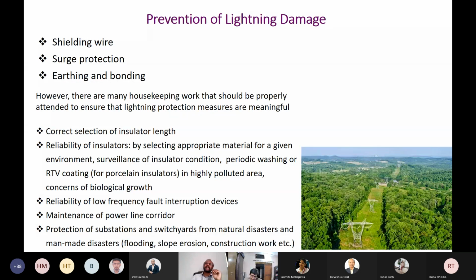Now, prevention of lightning damage. What are the prevention techniques that we use? Shielding wires, surge protection devices, then earthing and bonding. So don't forget that lightning protection is one comprehensive total scenario. You can't address only one part of that. This is something that I always advise to my clients, especially the clients from electrical networks or electrical utilities. People sometimes think that by doing one thing, they can get rid of the lightning damage. But usually it's a whole scenario where you have to address it as a turnkey project rather than giving partial solutions. So what are the things you can do?